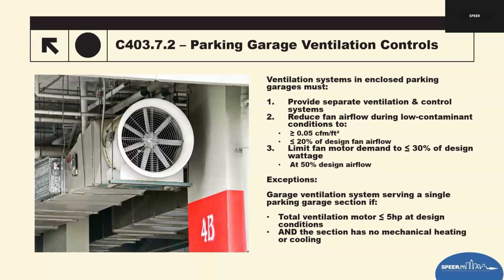Plan review tips: confirm whether the structure has multiple garage sections. If they do, they need to have their own system for each one. Verify each system has that dedicated control. Check fan schedules and sequences for turn downs that are less than or equal to 20%. And then validate the 30% fan watt limit at 50% airflow, probably in the manufacturer's information. And then ensure proper contamination detection for CO and NO2 sensors.